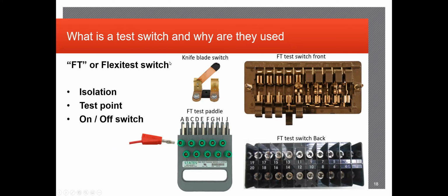All right, so FTs, or flexi test switches, I actually never knew what that stood for. We usually just call them FTs. There's quite a few variations of these, and their primary purpose is for isolation. It's an easy, accessible break between the relay or whatever other protection equipment may be associated. It's a great break between the relay and the actual circuit going out to the equipment out in the yard, whether it be a breaker or CCVT, et cetera, et cetera. So their primary purpose is for isolation.